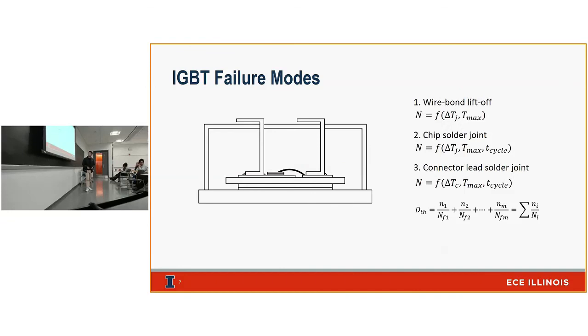We can find out how many of these sorts of stresses the IGBT module can endure, represented by big N, which is typically a function of the change in temperature, max temperature, and number of cycles. In this equation, big N represents the number of thermal cycles the IGBT module can undergo, and little n represents the number of cycles it has undergone so far. Summing these together gives a total damage fraction, and as this fraction approaches 1, we know the module has reached a failure state. This is called Miner's rule.